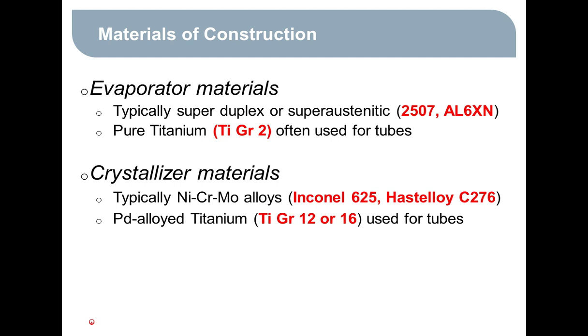And the crystallizer, because the concentrations of chlorides are even higher, we get into the Inconels, the Hastelloys, those high nickel, chromium, moly alloys that are pretty resistant to pitting and stress cracking corrosion. But they even are susceptible to it, so you have to be careful in looking at how low the pH goes. So that's definitely a concern. And then tubes, we still use titanium, but we add palladium to alloy with the titanium to make it even more corrosion resistant. So that's the grade 12 and grade 16 titaniums. Those are typically used for tubes.